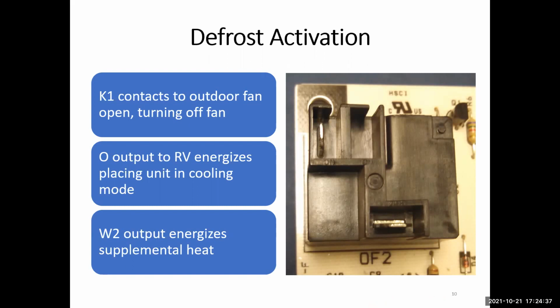So we're looking at the defrost board here. Here are the contacts that we're talking about for our fan. They're considered K1 contacts. The outdoor fan opens, turning off the motor. When the defrost is activated also, your O output to the reversing valve is placed in cooling mode, with obviously the exception of the outdoor motor. And your W2 output energizes the supplemental heat.